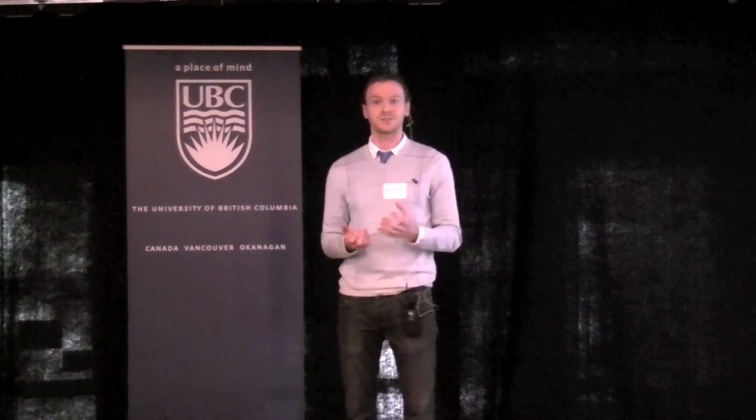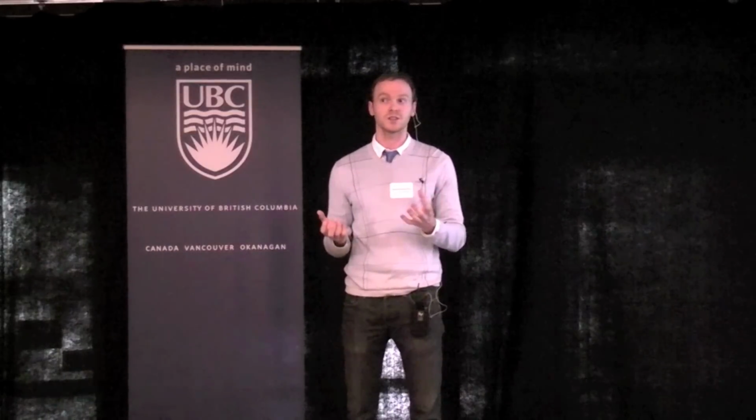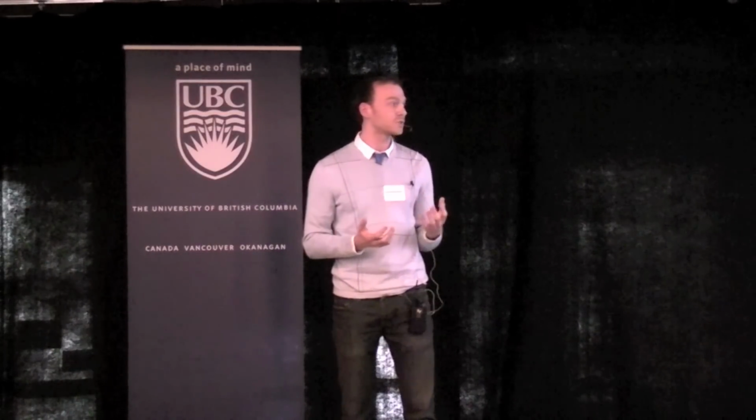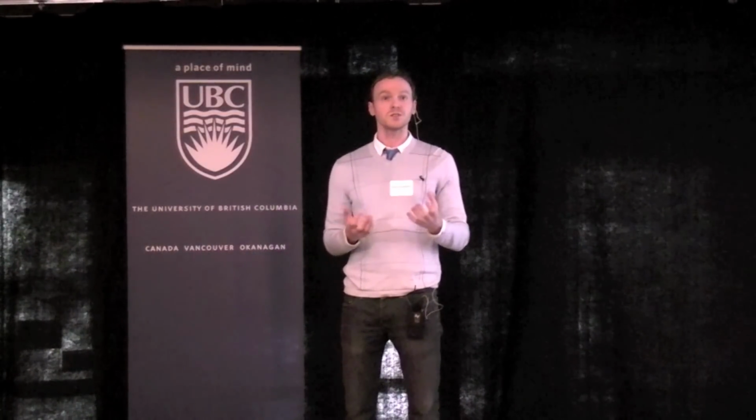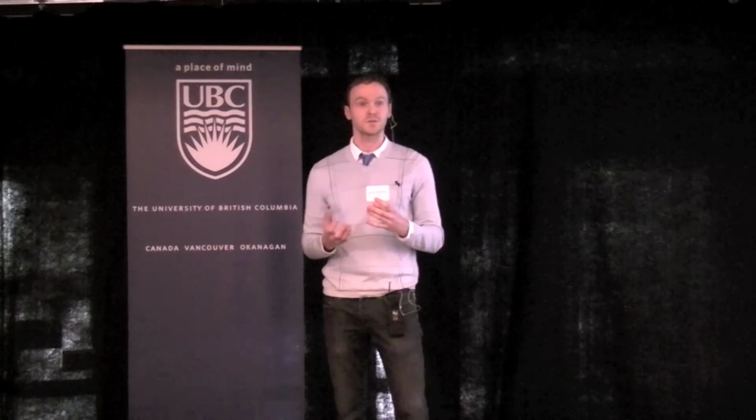This is filtering on a macro scale, and since what I look at is micro and nanoparticles, I have to also look at the filter from the micro scale. To do this, I investigate filter properties, such as the fiber size, the packing density, and the general layout, to understand how this affects the energy use. I also take a look at the particles that build up themselves, since this is what we're actually filtering. And we notice that as a filter operates and you accumulate particles, the energy cost starts to increase. And we want to understand how we can manage this energy cost.